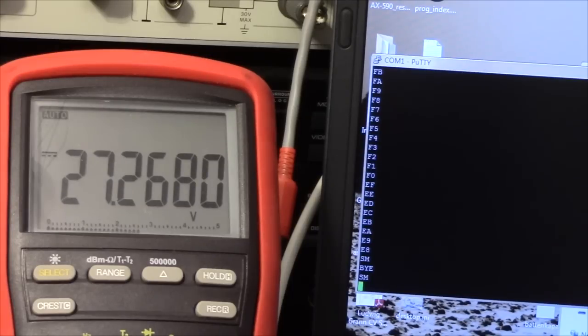However, another thing you want to do is if you get one of these units and you put new batteries in it, it won't calibrate properly unless you manually adjust the battery constant, which essentially tells the unit the capacity of the batteries. I haven't gotten any new batteries for this unit yet, so I'm not going to bother doing that right now, but essentially it's the same procedure, but you send the unit another command in order to adjust another variable, and you set the variable to reflect the capacity of the batteries. You might need to experiment a bit on it.